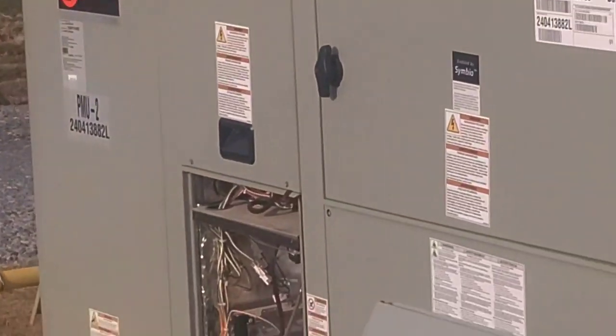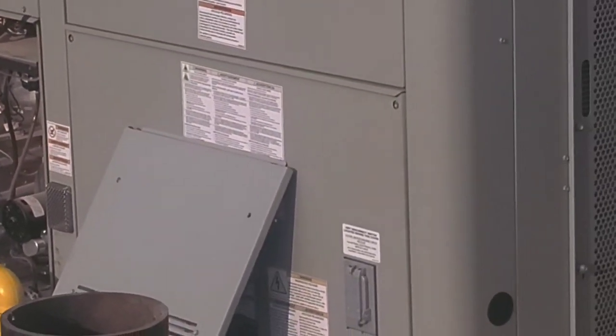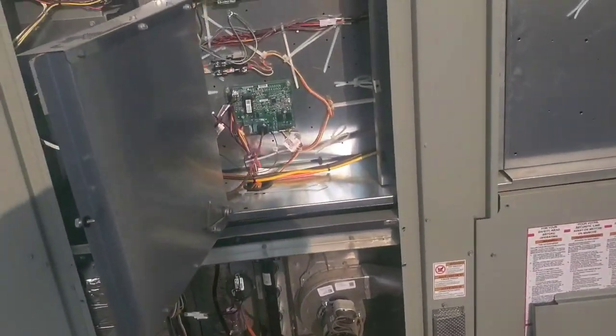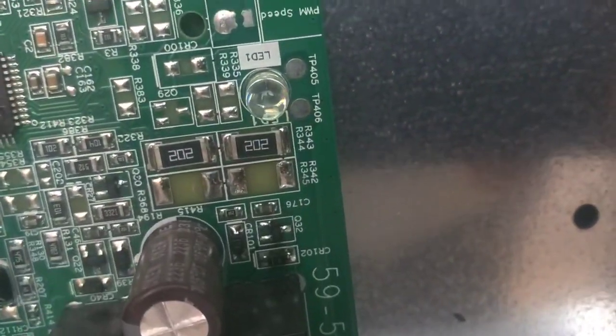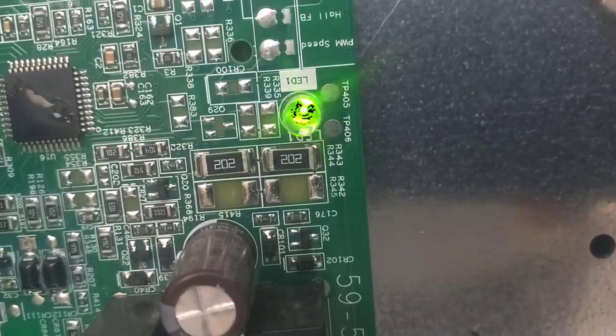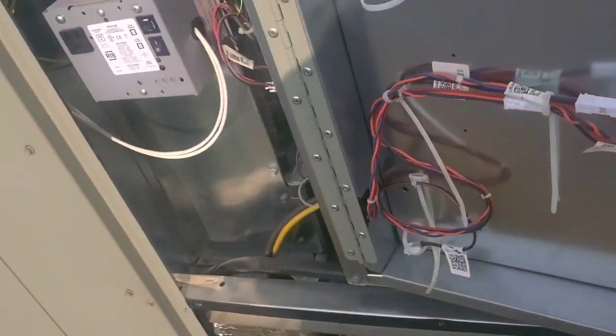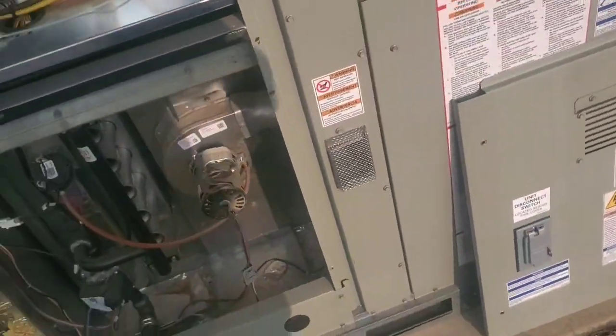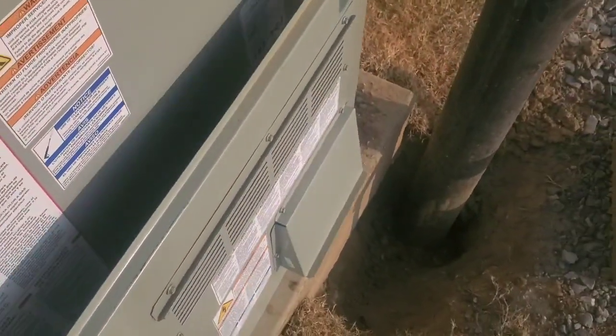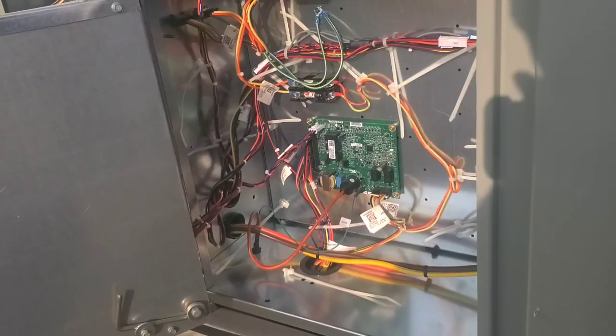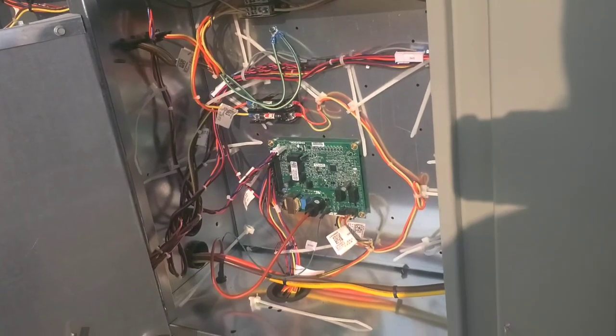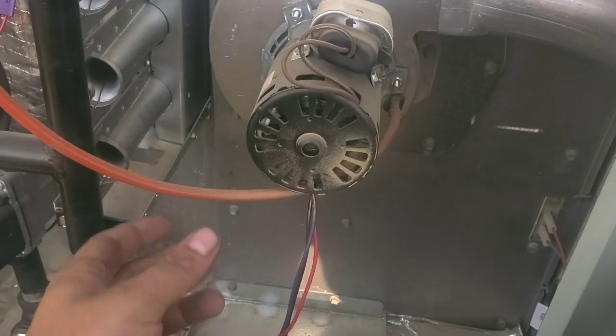This unit over here is heating just fine. But this one has decided it wants to do whatever the hell it pleases. We got an obvious 3 blinks code. Obvious except that there's no legend anywhere inside the unit that tells us what 3 blinks actually means. So we're just kind of on our own as far as that's concerned. Google says 3 flashes means pressure switch. Well, that's pretty likely.